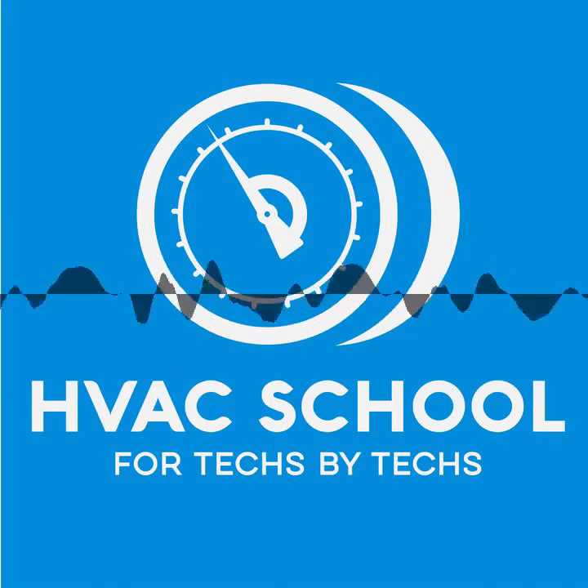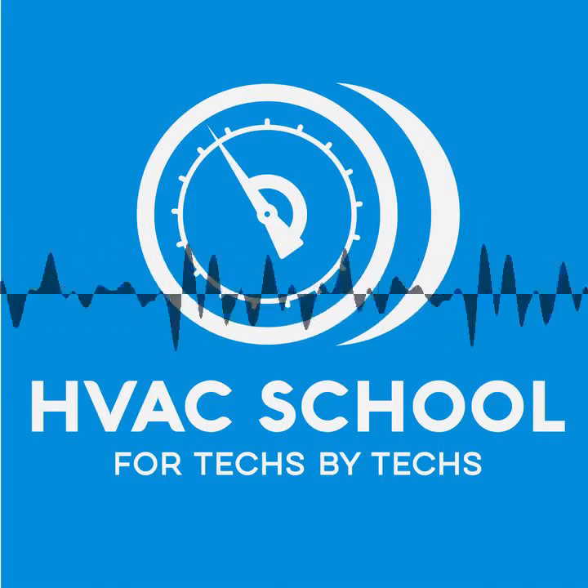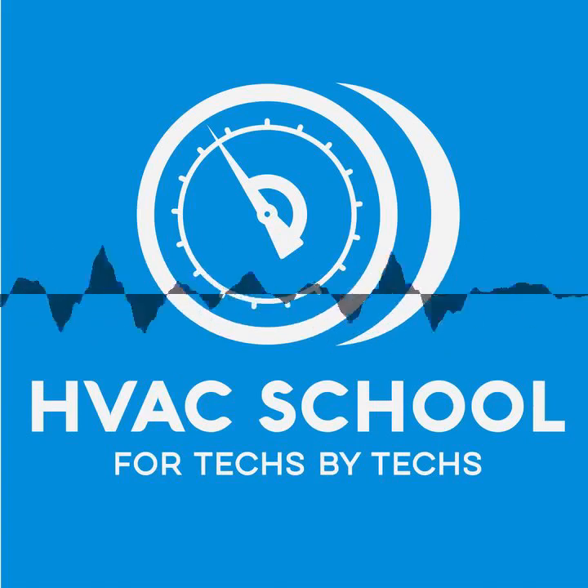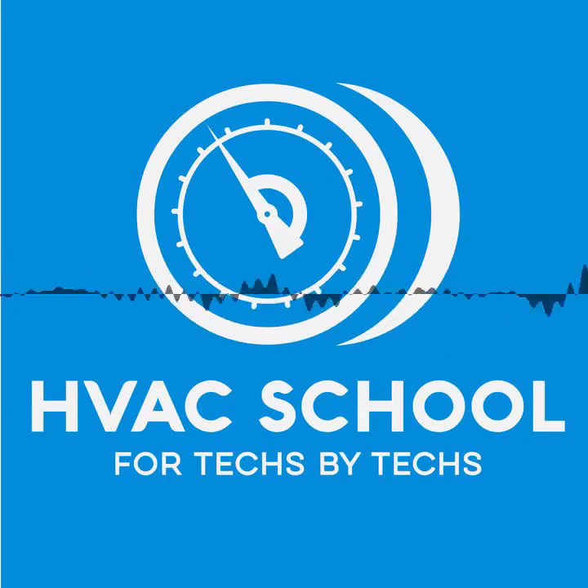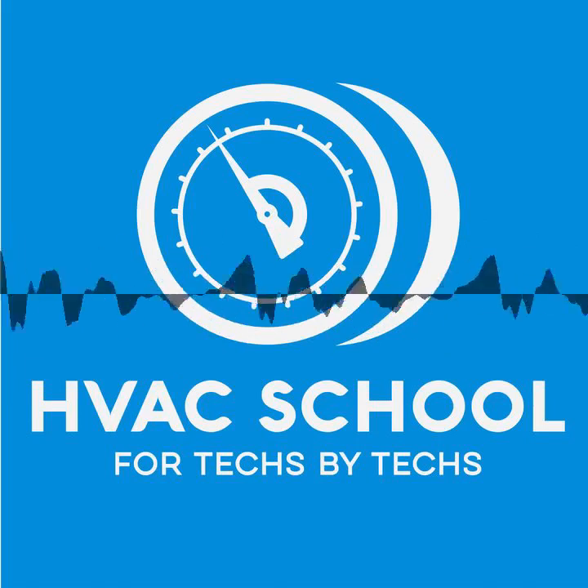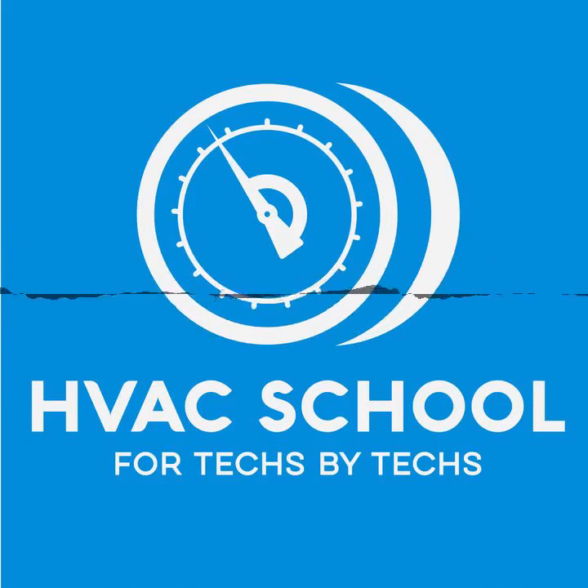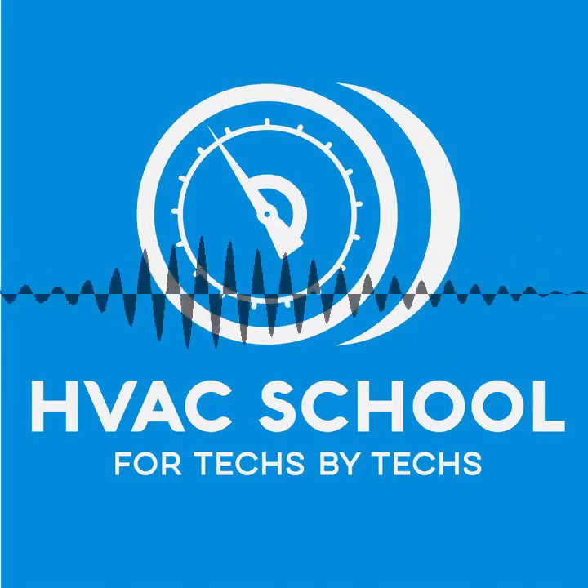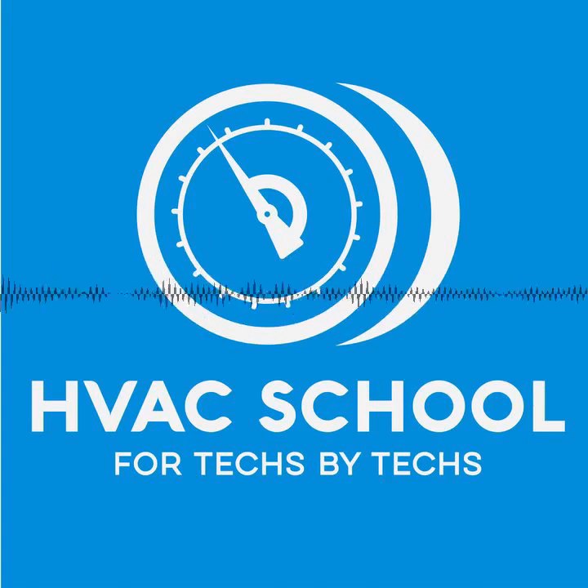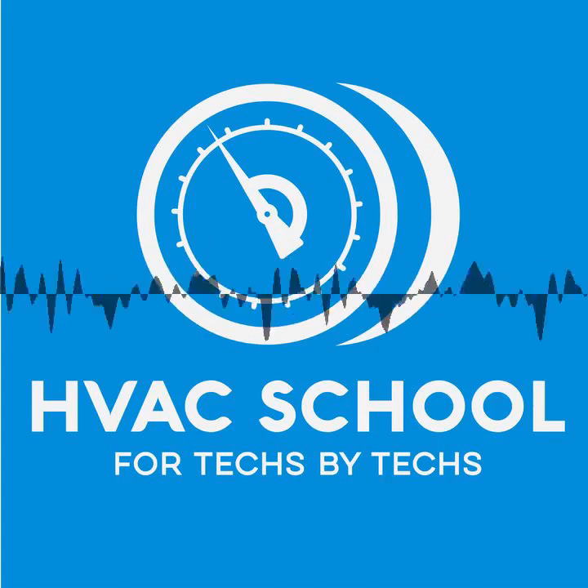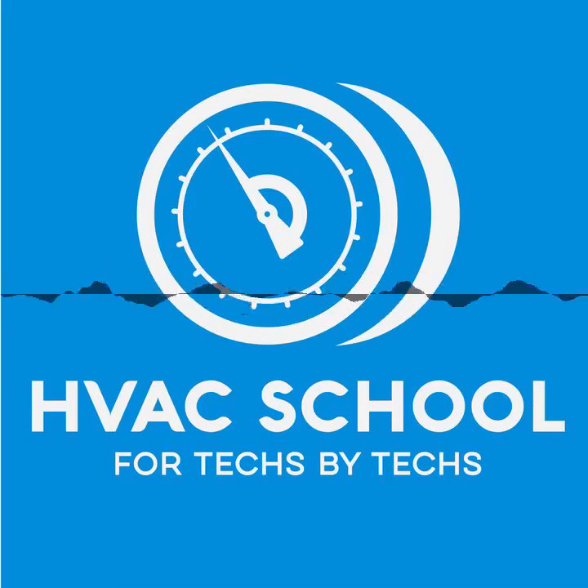So, rule of thumb, what I would do is that it has a test mode where you can put the compressor at 100% speed, and I would check the room temperature and go from there for a ballpark figure. But the electronics usually do the rest. And on a lot of these systems, you can monitor superheat and subcool for the individual air handlers, can't you? Yes, you can. On the controller, it'll let you see the superheat and subcool for each one, and it shows what the electronics are looking for and the actual value.